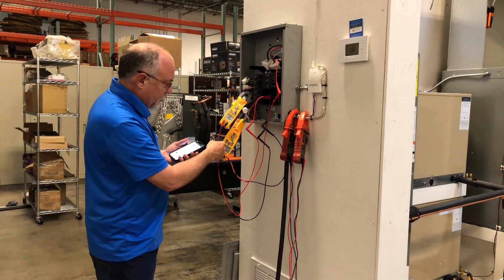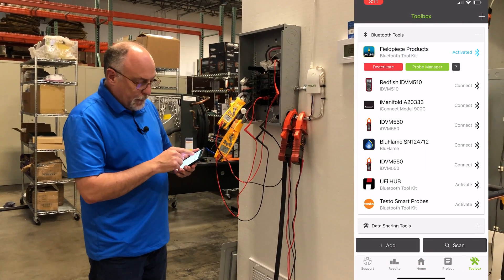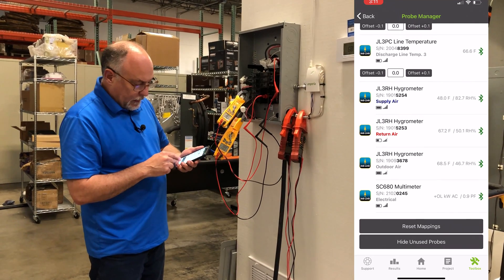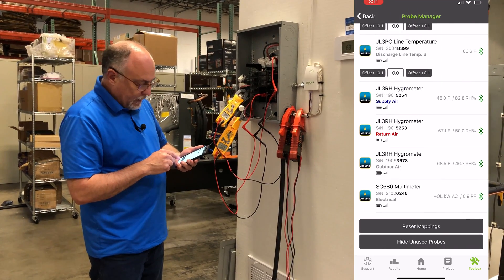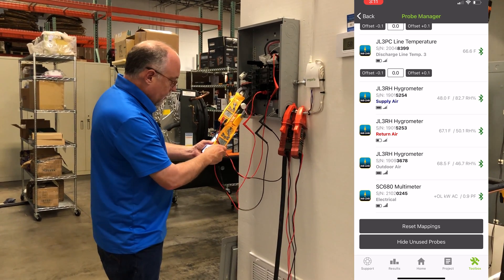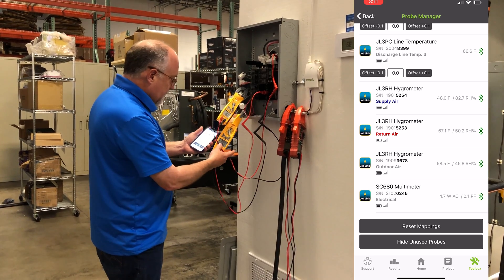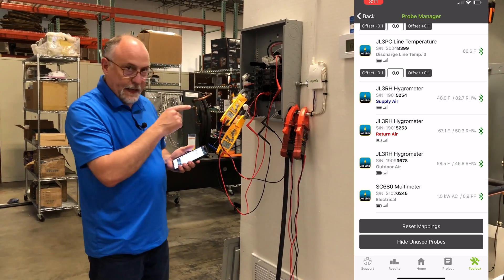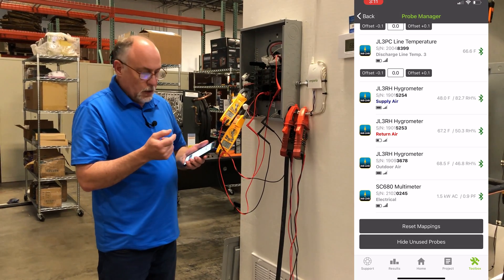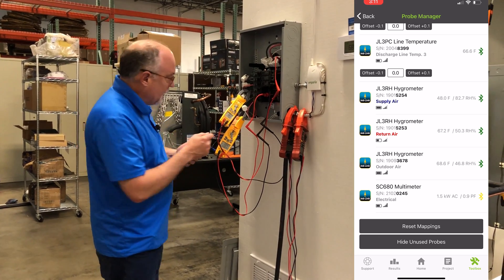Now I'll be bringing in power factor and power on both meters. In your toolbox, if you turn on Fieldpiece meters or probes and scroll down, you're going to see your multimeters here. One of them is showing OL because its polarity is reversed, so I'm going to have to swap these two around. The meter is polarity sensitive — if you're measuring on the red wire for voltage, you've got to be on the red wire when measuring power as well. Now you can see it's coming in at 1.5 kW.